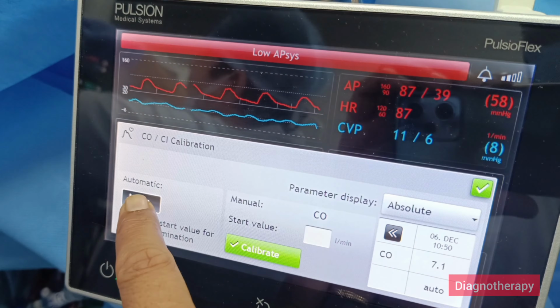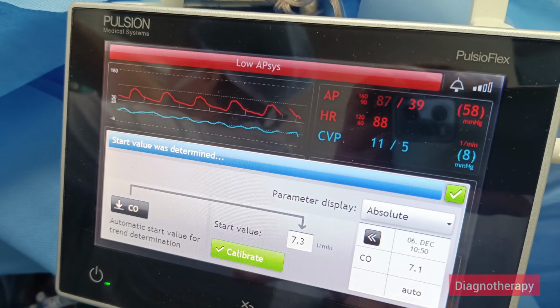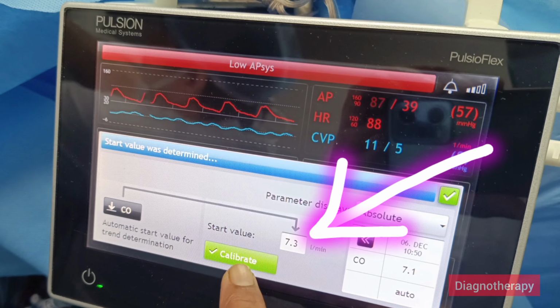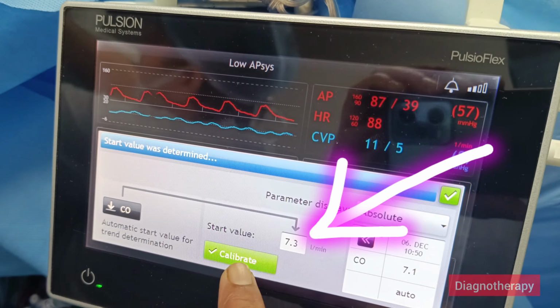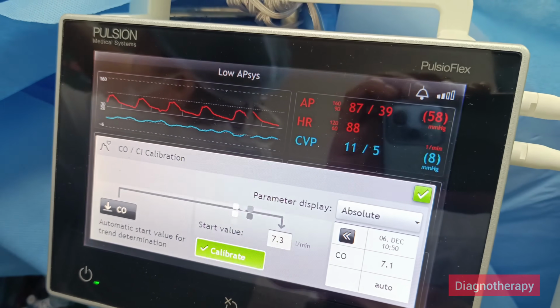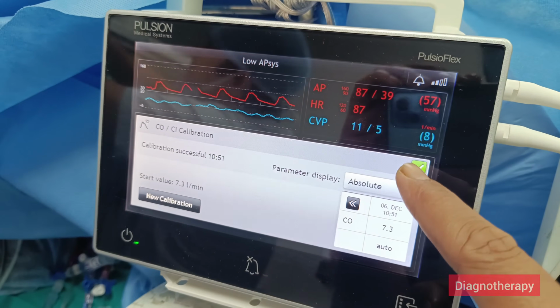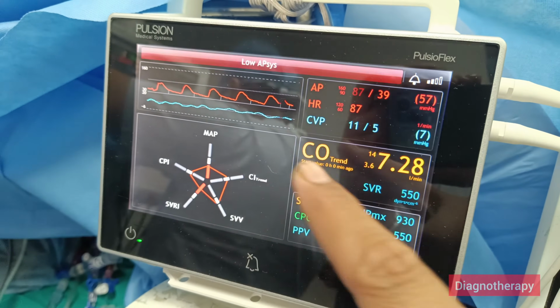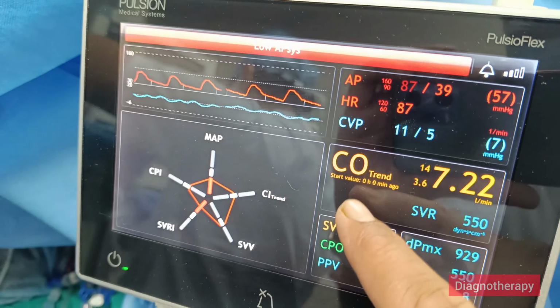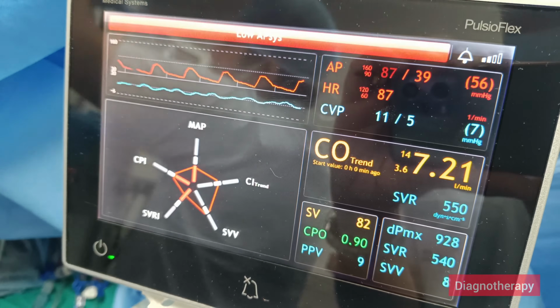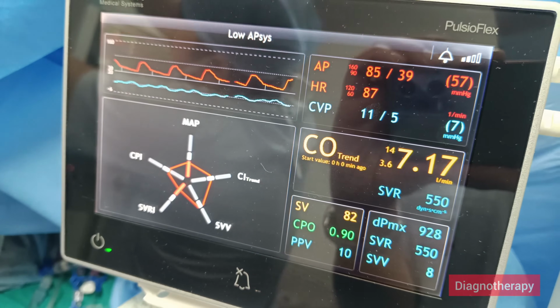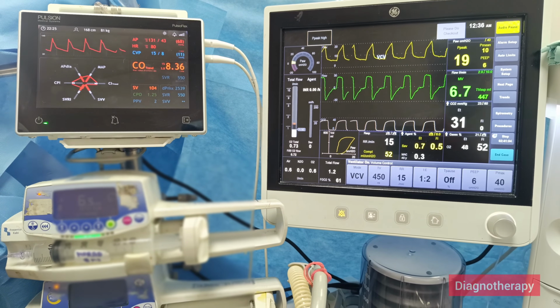Then we need to place the CO button in automatic. After the values have started coming and it is fixed, we need to press the Calibrate button. After this, we need to press on the tick mark. Then it is calibrated.